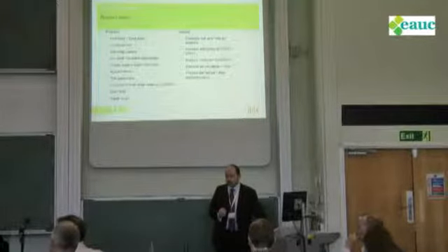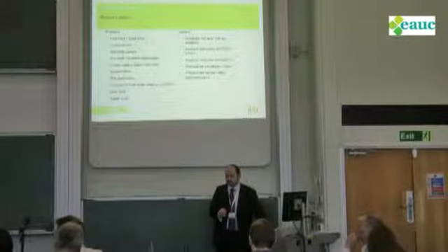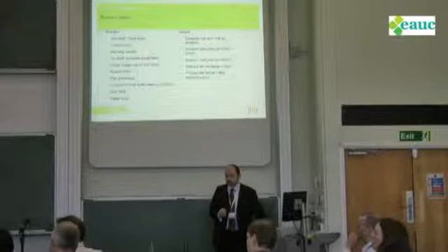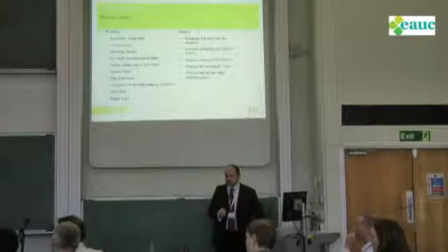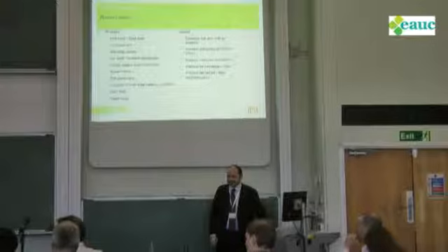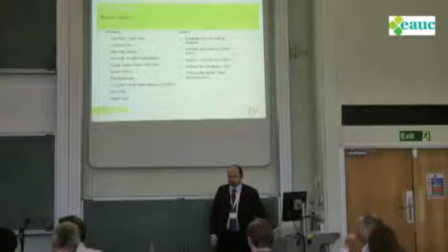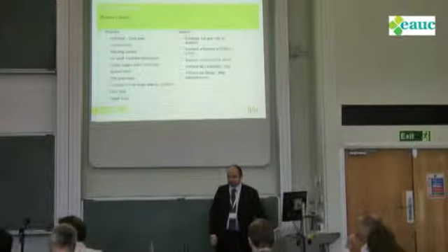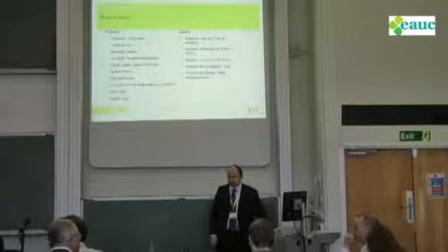If I can add to that, it's kind of counterintuitive. You've got an IT department, they've got hotspots in their data centre, which is often a problem. So what do they do? They need more air, so they turn the fan speed up, and of course what that actually does is make the problem worse. So it is counterintuitive, but by slowing the fan speed, you can actually get better air distribution through the room. And of course, you're actually using less energy with the fans as well. So it does work differently to how we might imagine.